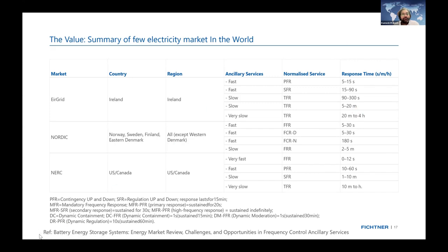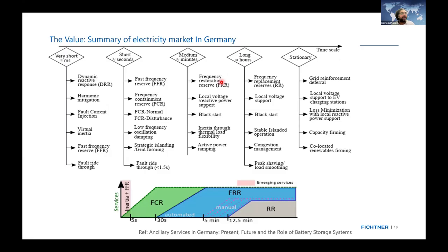Okay, now I want to finalize this with the overall futuristic aspect of the application. In a very short time period, we have dynamic reactive response, harmonic mitigation, fault current injection, virtual inertia in terms of grid stability. As inverter-based resources become more common in day-to-day life, the rotating elements, the rotating spinning reserve or synchronous condenser, will not be there to provide your inertia. So you need virtual inertia for that.